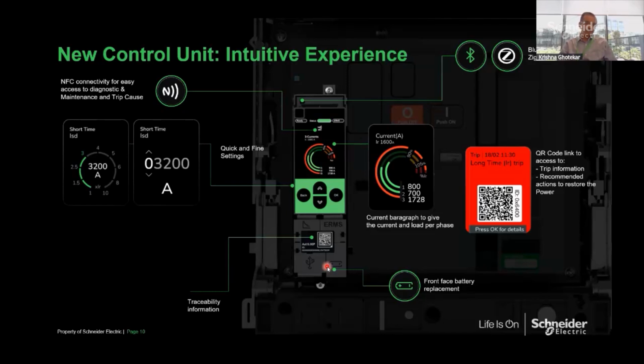Another challenge which we faced in the past, not only Schneider but most of the manufacturers, is the setting of a breaker. Today, what we can set is in terms of steps. Let's say for an overload or a short circuit, this is a 1600 amps breaker, you can set it like 1.5 times, 2.5 or 3 times. But sometimes, as per the fault calculation study or as per the selectivity or coordination, the consultant needs it to be set not at 3200 but at 3100 or let's say 3150. Now today, because it's between the ranges, you cannot set in between.